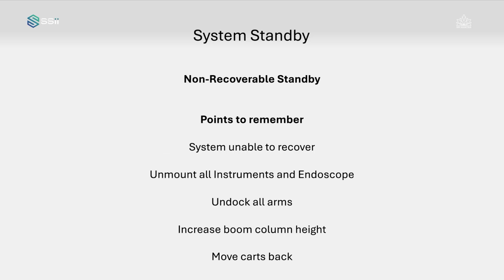In case the system cannot recover automatically, it may have encountered non-recoverable standby. Kindly follow the undocking sequence as stated. First, unmount all instruments and endoscope from the system. Second, undock all the arms from the patient trocar. Third, increase the boom column height of all patient side arm carts. Fourth, move all the carts back, removing them from the patient area.